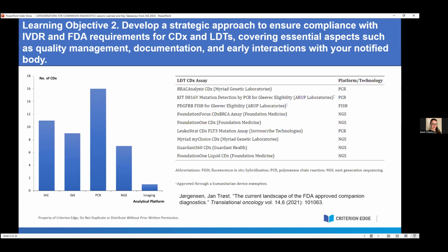Several of the companion diagnostic assays on the FDA's list of cleared or approved devices also fall under the realm of being a laboratory developed test, or LDT. And many of those have still been cleared through the submission of a PMA. In fact, as of the publication date of this particular review article, there were a total of 9 companion diagnostic assays, mostly PCR or next generation sequencing based assays, that were lab developed tests. And for each of these assays, it's clearly stated in the intended use that the assay can only be used at a single specified laboratory site.